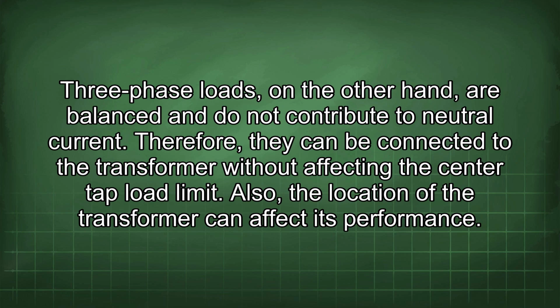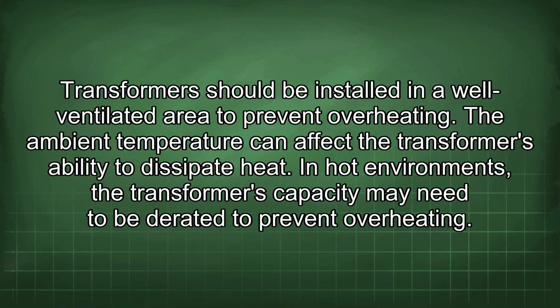Also, the location of the transformer can affect its performance. Transformers should be installed in a well-ventilated area to prevent overheating. The ambient temperature can affect the transformer's ability to dissipate heat. In hot environments, the transformer's capacity may need to be derated to prevent overheating.